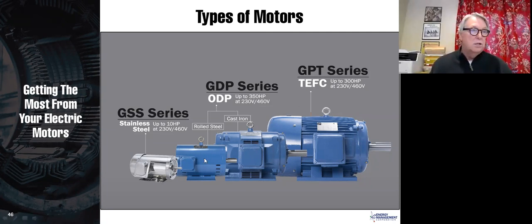So this is a rolled steel motor. We just roll it in steel and stuff the motor inside of it. This is kind of your cheapest sort of motor. This is an open drip proof, so the cooling air actually goes through the motor. This is a cast iron open drip proof, ODP, and the cast iron open drip proof has a cast iron shell, so it's very, very stiff. That keeps the bearings in alignment, and bearings are the #1 cause of motor failure. So much, much better motor, but it still has air going through the motor, and so it should be only used in clean environments.